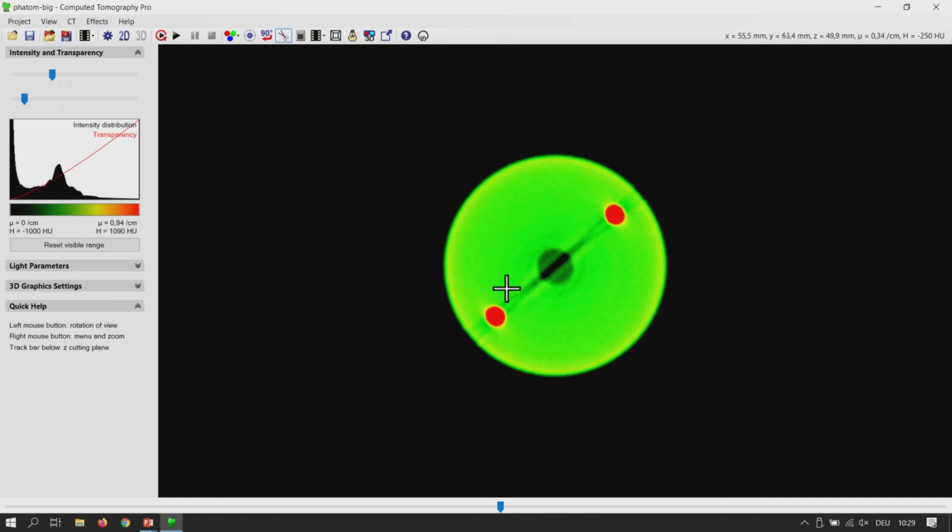For example, a computed tomography of the neck is hard to do or barely impossible if that person has metal tooth fillings. So they are always absorbing the radiation and standing in the way. And they do produce artifacts, clearly visible here. And so the image quality is degraded intentionally. And this is exactly what we wanted to show with this phantom.